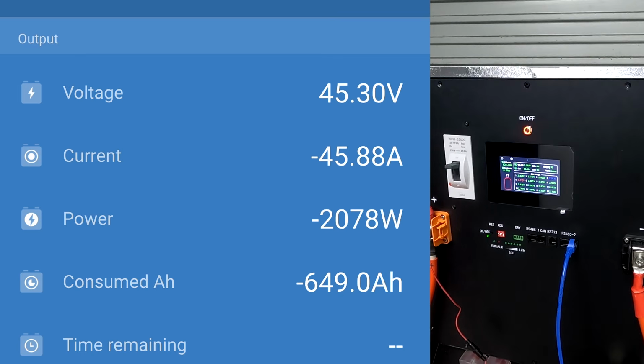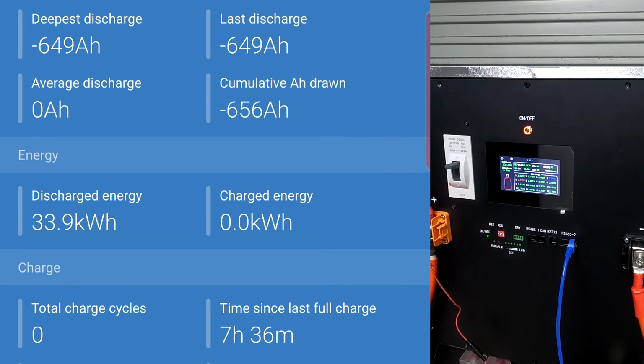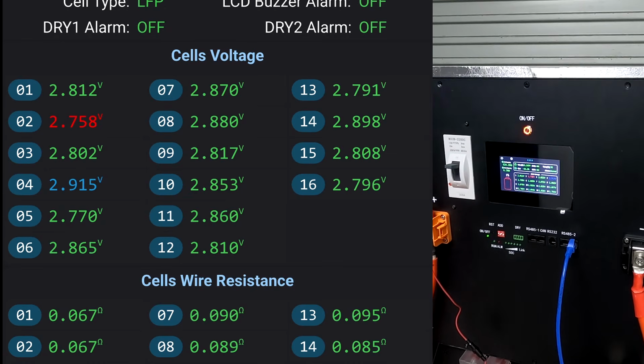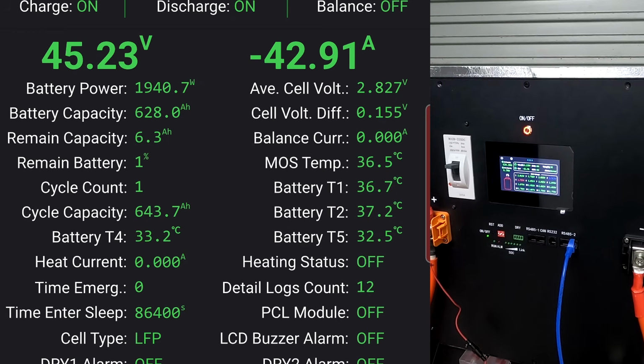We just hit 649 ampere hours. Do we see 34 kilowatt hours? Yes, we will. Cell number 13 is at 2.79, along with cell number 5 and cell number 16. We've got 156 millivolt deviation now. At this low voltage, 45 volts, 150 millivolt deviation is actually pretty good.